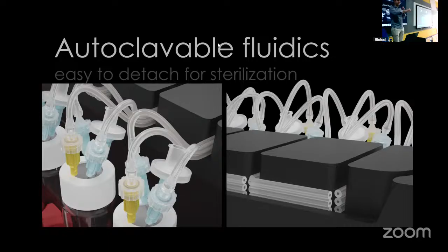The whole device was designed for exactly this procedure. It has really a lot of silicone tubing that I'll take out from my bag at the end, and you can touch it, you can see it, but it's very easy to attach and detach from the instrument. So if something happens during startup, if you put your finger where you contaminate, or if you open the vial and something gets contaminated, it's not a problem. You can very easily autoclave, then you're sure it's sterile.